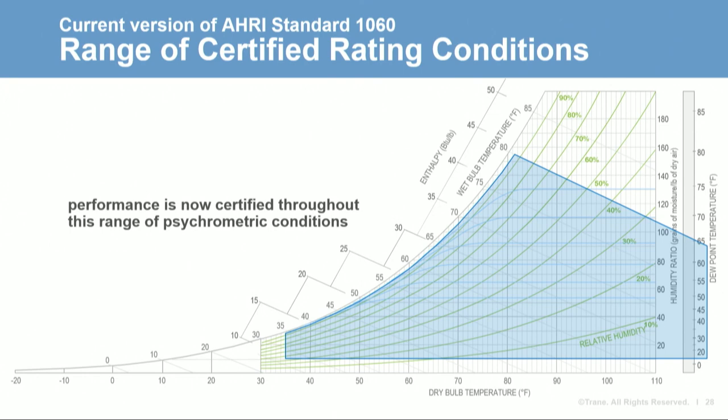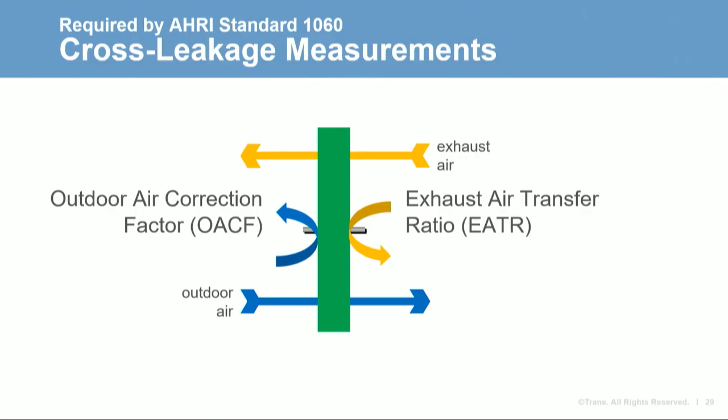In addition to effectiveness and air pressure drop, the AHRI rating standard also requires measurement of cross leakage — air that leaks through the device from one airstream to the other. For some applications, leakage of exhaust air into the entering outdoor airstream could be dangerous, so it needs to be avoided altogether. But for the vast majority of applications, cross leakage is not problematic as long as it's not excessive.